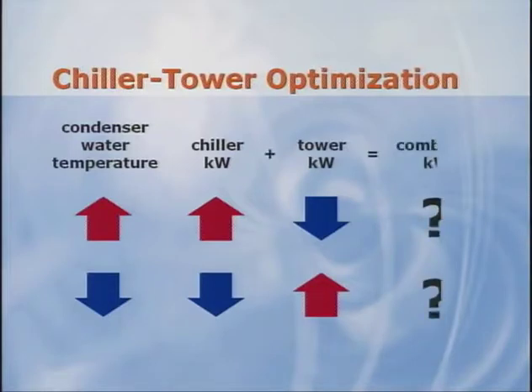The question is, what's the impact on the combined energy of the chiller plus tower fans? And what is the temperature that results in the lowest combined energy use? The answer is, it depends. And this optimum temperature changes as conditions change. The chiller tower optimization strategy uses the chiller plant control software to determine this optimum condenser water temperature set point at any given time to minimize the combined energy use of the chiller and cooling tower.